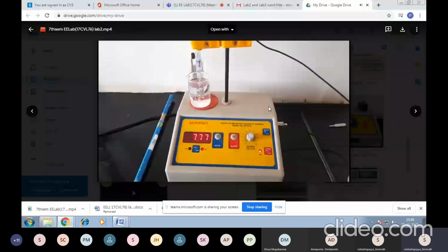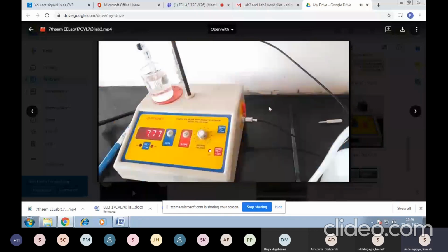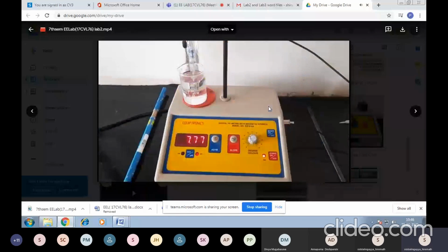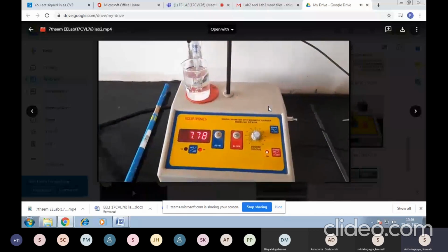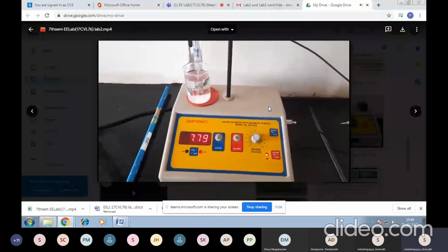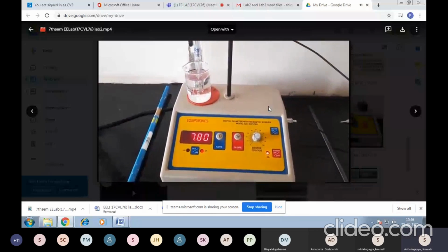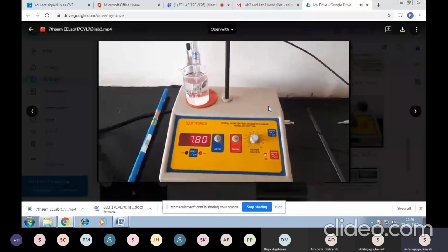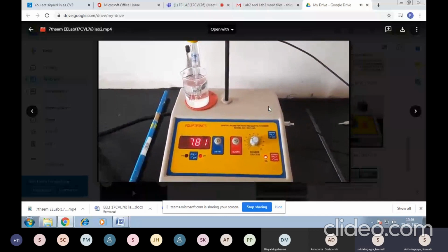Temperature knob. The EMF by electrode is temperature sensitive. This control compensates for temperature dependence of electrode output. The dial has to be set to marking corresponding to the temperature of the solution under test.